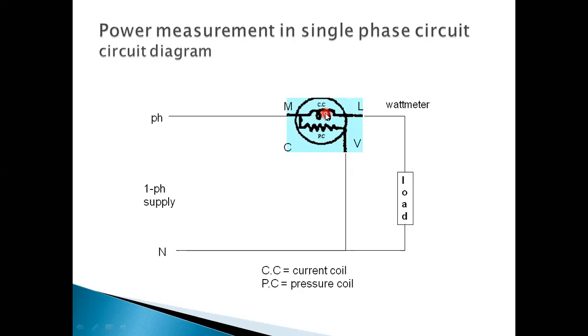So we'll have 2 metal conductor strips, visible on the case of the wattmeter, where we can connect the 2 strips either in series or in parallel. When they are connected in parallel, the same wattmeter is used for higher current rating. When they are connected in series, the same wattmeter will be used for low current rating.